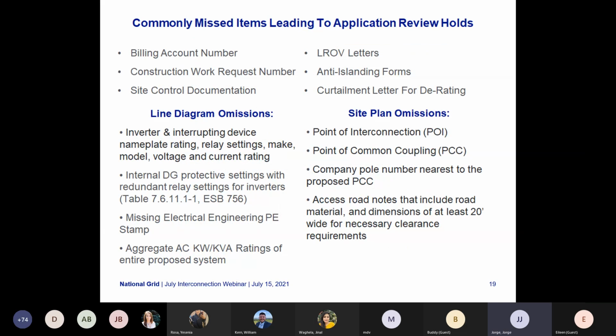Next slide, please. On the application, some of the commonly missed items that lead to application holds during the process are missing billing account numbers, missing service work request numbers, missing site control, load rejection over voltage letters, anti-islanding forms, and curtailment letters. On the line diagrams, missing electrical PE stamps and protective settings for the relaying. On the site plan, missing the point of common coupling or the nearest company pole number or piece of equipment near the site to determine where we're going to have the POI for the site, and then the 20-foot wide access road comments so that we know we can get our personnel and equipment to the site. Next slide, please.